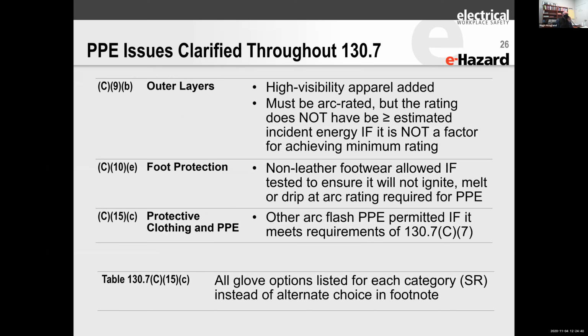PPE issues that are clarified. This section, I think these are all my proposals. Yes, they are. Outer layers, high visibility apparel has been added to outer layers. It must be arc rated, but it doesn't have to be greater than or equal to the estimated incident energy. So the reason here was a lot of people were going out and buying 8-calorie vests and then wearing an 8-calorie shirt underneath them.